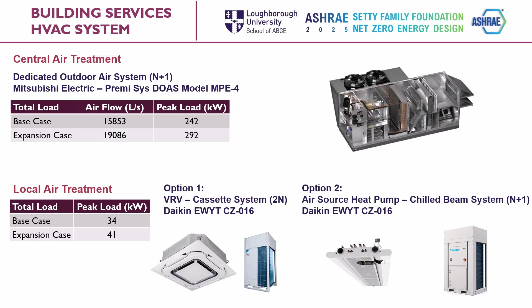The central DOAS system will supply a base case of 16,000 liters per second of airflow with a peak thermal load of 242 kilowatts. The expansion case will have a peak airflow of 19,000 liters per second with a peak thermal load of 292 kilowatts. The DOAS system will be sized for N+1 redundancy.